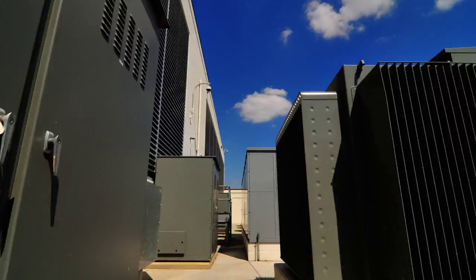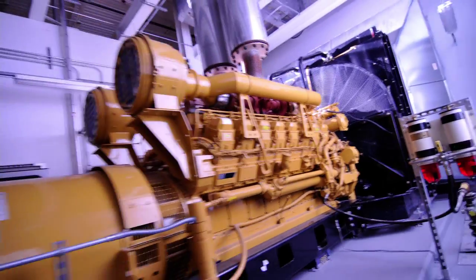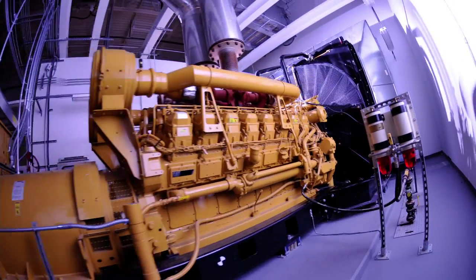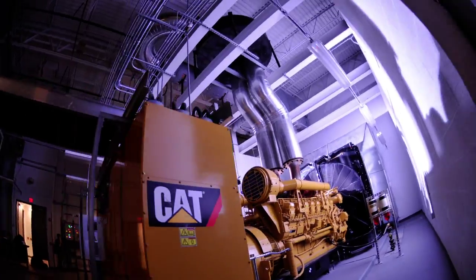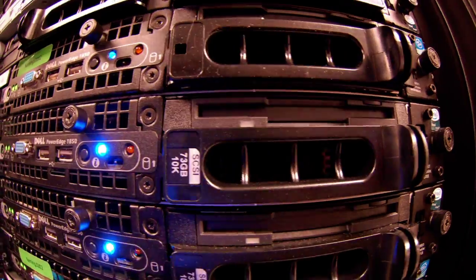Within each pod, there's separate power sources, and we have generators that are on top of that providing the redundancy. A generator needs 20 to 30 seconds to start. You don't get a 20, 30 second warning on the outside power source. So we have 3 battery units feeding the 6 pods with one as backup. We have multiple telcos coming into the building. Separate feeds from 2 different carriers.